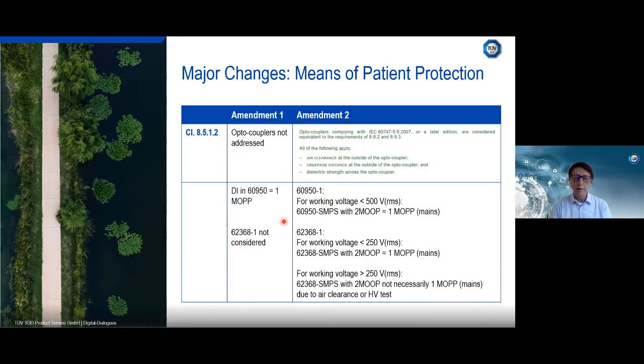In the new edition, we can use 60950 equipment and also 62368 equipment. An important thing is that when you use 60950 equipment, the two means of operator protection included in the power supply with 60950 can be used as one means of patient protection. This applies for working voltages below 500 volts.